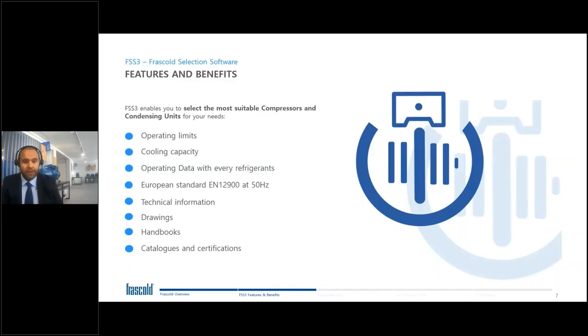Simulation with the most common refrigerants in the market you can find in our software. For refrigerants that are not included in FSS3, we can provide special selections on request. For all polynomial data, the reference is EN 12900, which prescribes in general for reciprocating compressors a return gas temperature of 20 Celsius with 0 K of subcooling at 50 Hz, and for screw compressors 10 Kelvin of superheating, no subcooling, always at 50 Hz. For each compressor, it is possible to have dedicated technical information, drawings, and links to handbook, catalog, and certification directly from the software.